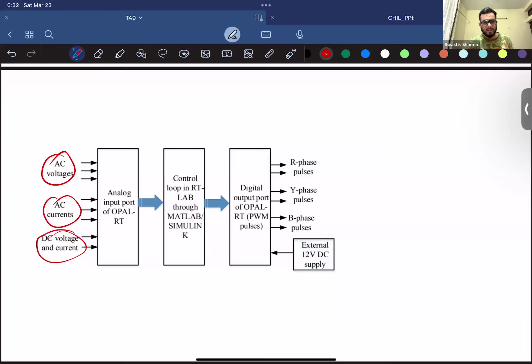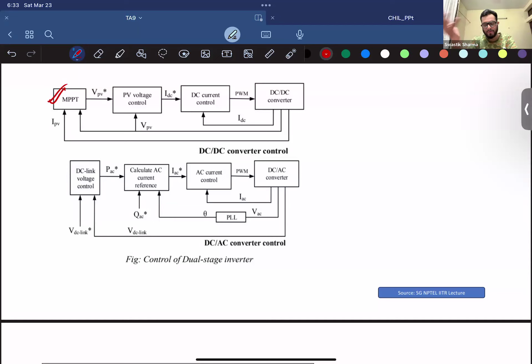So a dual stage converter-inverter is something very similar. It's used to implement control for both converters, the boosting stage as well as the inversion stage. Since you have first the boost converter and then your inverter, you first implement the control logic for your boost converter, which is then used to give the DC link reference, able to provide pulses for the DC-AC conversion stage.